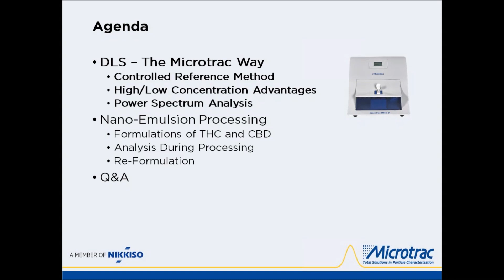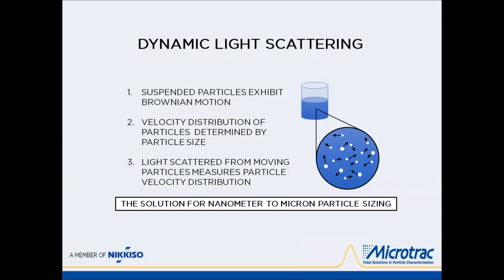Thanks, Kelly. So I'm going to talk about dynamic light scattering the Microtrac way, and then step into the nanoemulsion processing that I did. But let's go ahead and start off with dynamic light scattering. So these are the three main rules when it comes to dynamic light scattering. The particles have to be dominated by Brownian motion of the matrix, which means whatever liquid your particles are in, that liquid has to be imparting motion on the particles. And the velocity of those particles is directly related to their size. Big particles move slow, small particles move fast. And that's the general principle when it comes to dynamic light scattering. All of the light scattered from those moving particles is what we use to generate our particle size distribution. It is a great solution for anything from 4 to 5 microns down into the sub-nanometer range.